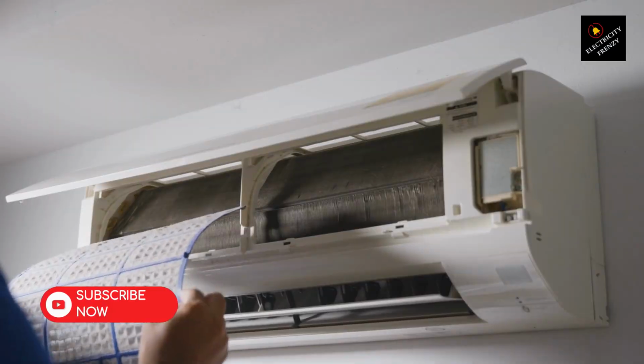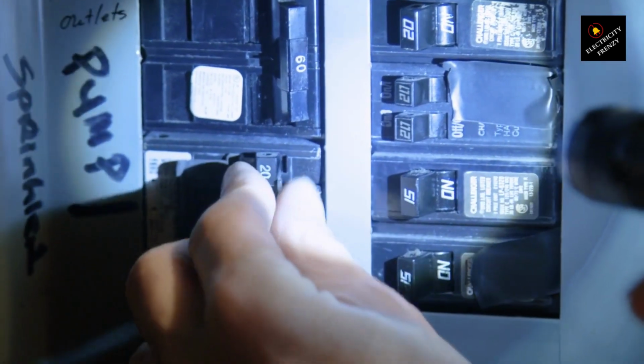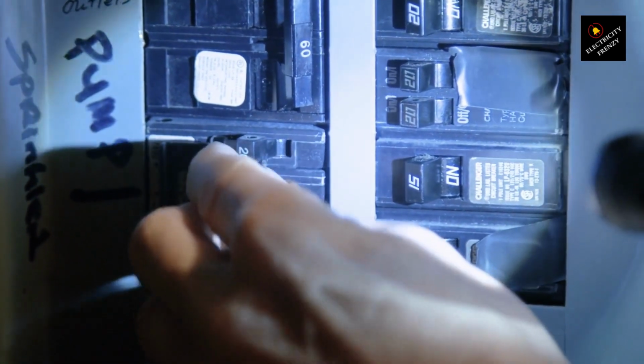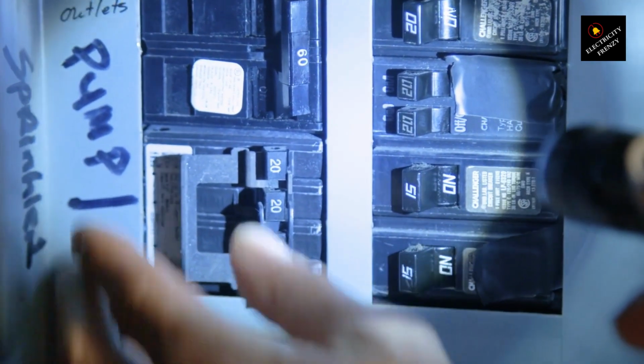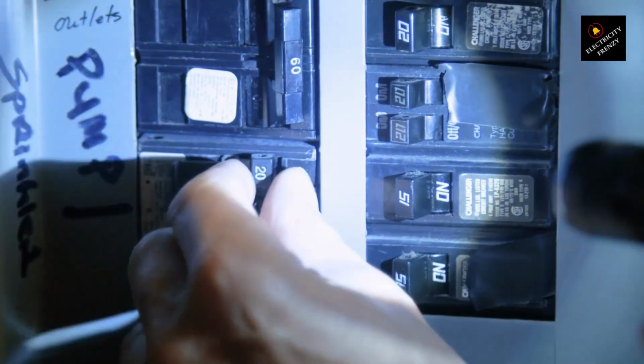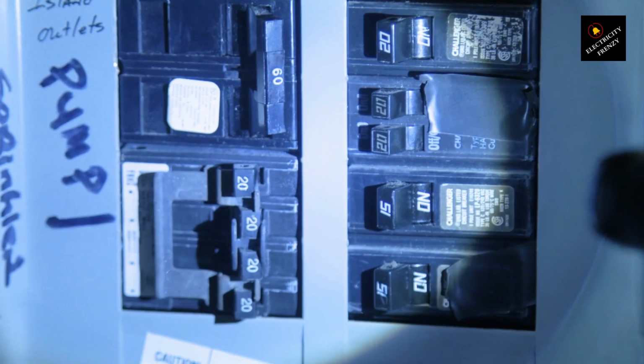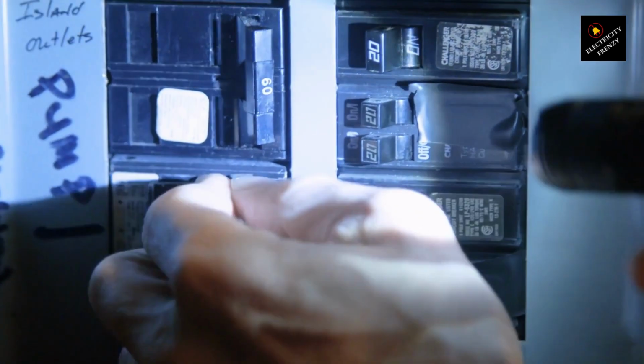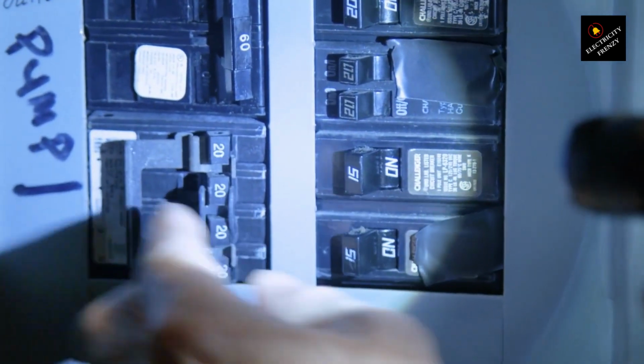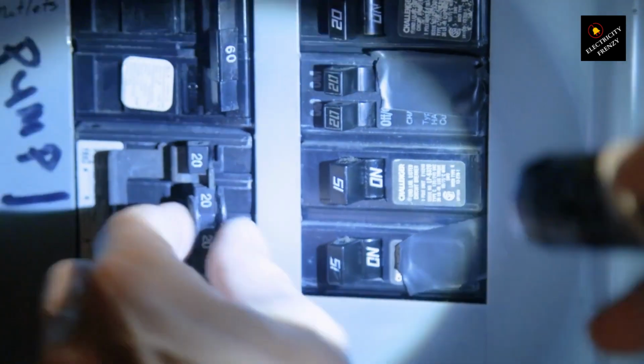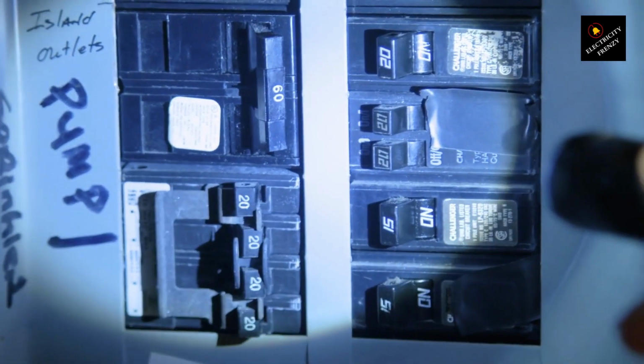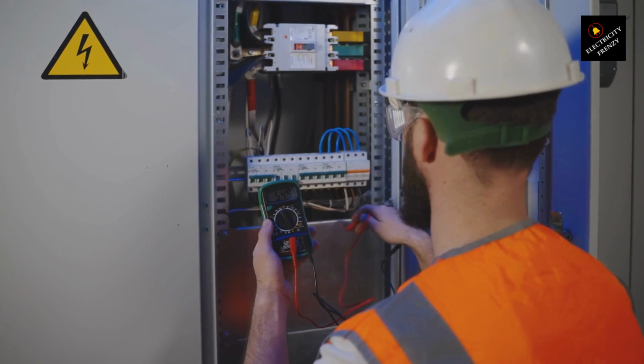Solution: if a refrigerant leak is detected, it's important to have a professional HVAC technician repair the leak and recharge the system with the appropriate refrigerant. Refrigerant handling requires specialized knowledge and equipment, so it's best left to the experts. We mustn't forget about compressor issues. A malfunctioning or failing compressor can draw more current than usual, overpowering the circuit and resulting in a breaker trip.